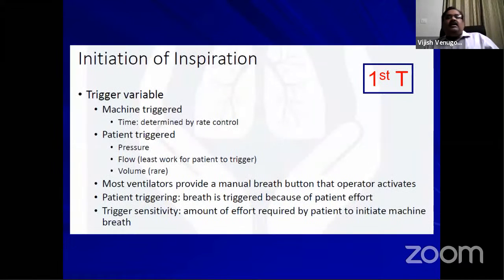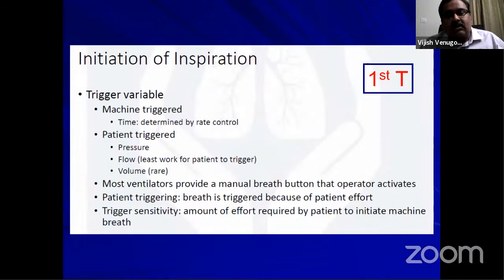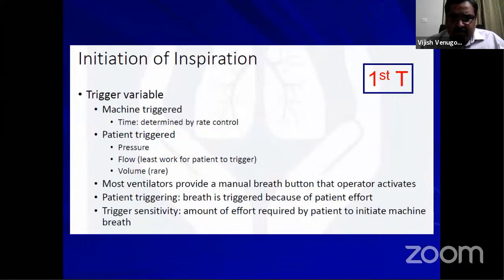The first T is the trigger, which will initiate an inspiration. So the trigger variable could be either machine triggered or patient triggered. All machine triggered breaths are time triggered because it is determined by the rate that you're setting on the ventilator. Patient triggered ones could be triggered either by pressure or by flow. Volume is very rarely used. Most ventilators will even give you an option of a manual breath button. So in patient triggering, the breath is triggered because of the effort that the patient puts in. So there is an important factor there, the trigger sensitivity.